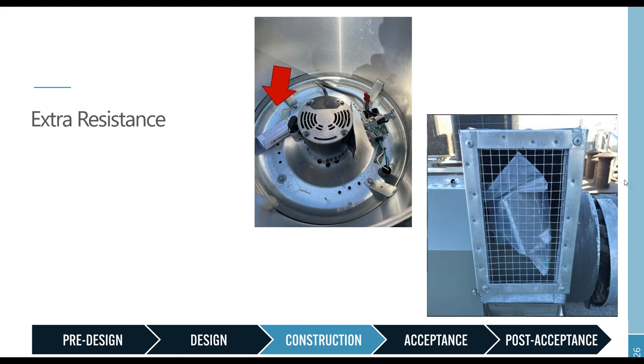The photo on the right here was actually an example of a project that was, once again, trying to get approval for occupancy so that people could move in. And what was happening was they were not able to meet their airflow set points. And this became a process of back and forth of blaming the engineer for incorrectly sizing a fan, for then going back and blaming the contractor for incorrectly installing it. But in the end, what it came down to, this photo on the right, was simply a bag stuck in the bird screen, adding extra resistance and stopping the fan from performing the way that it should. So in this case, luckily, it was a very simple fix, but something that had still been missed by multiple other sets of eyes that was getting in the way of allowing occupancy for this project.